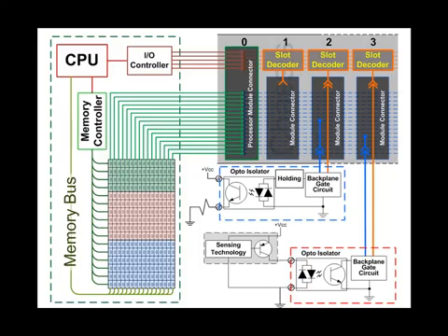During the input scan, the processor activates the input modules in numerical sequence. We only have one card in slot 3. The processor sends a signal across the control bus, and the decoder at slot 3 reacts, enabling the backplane gate circuits of all 16 inputs connected to the module in slot 3. And whatever the state of the inputs are in, this is felt at the memory array in the processor by way of the backplane.